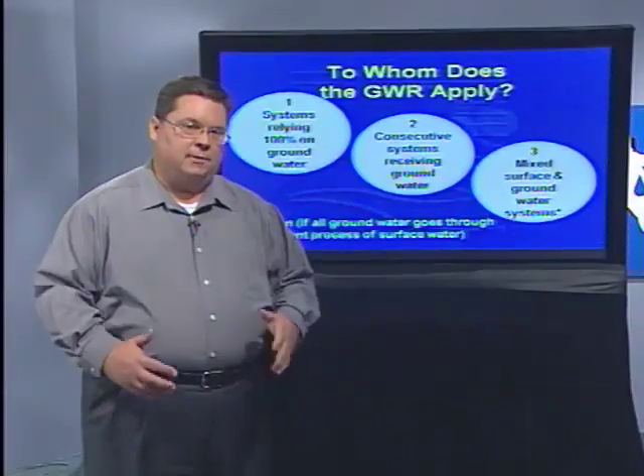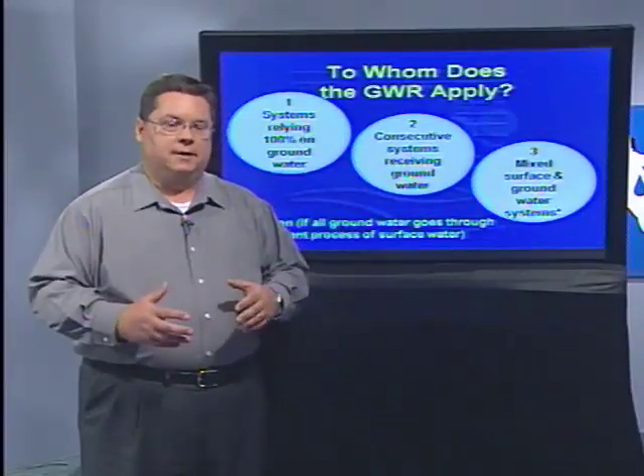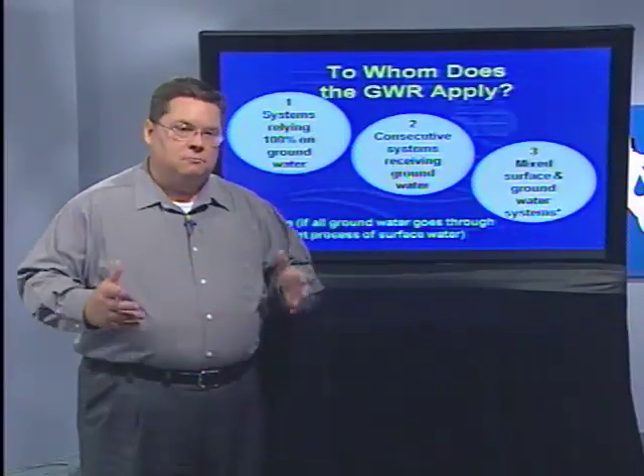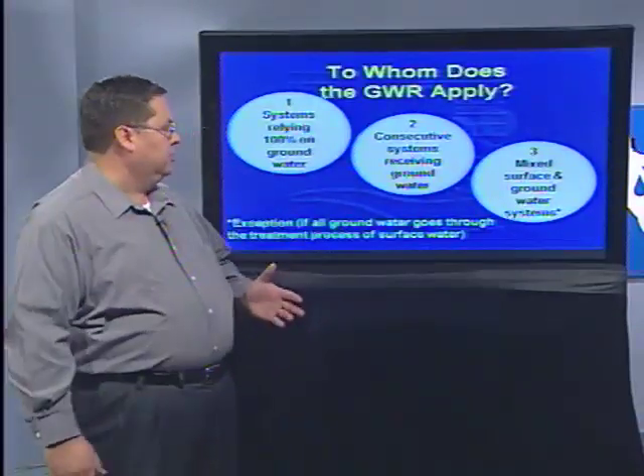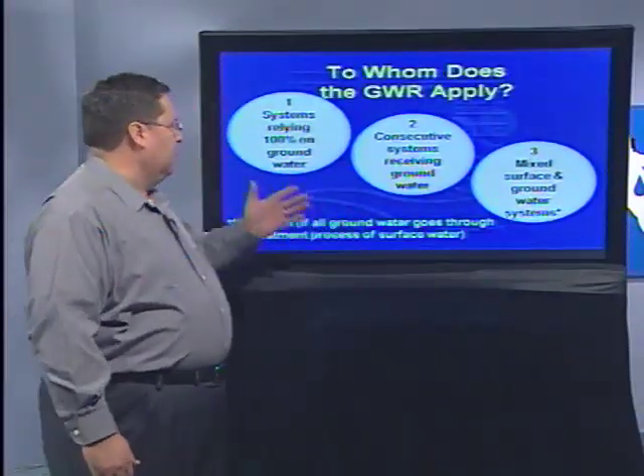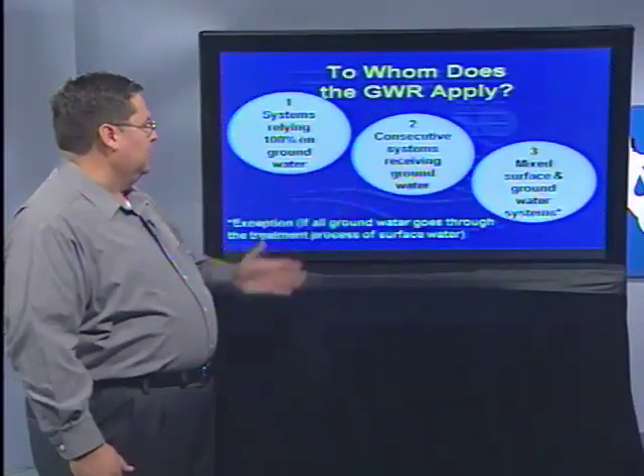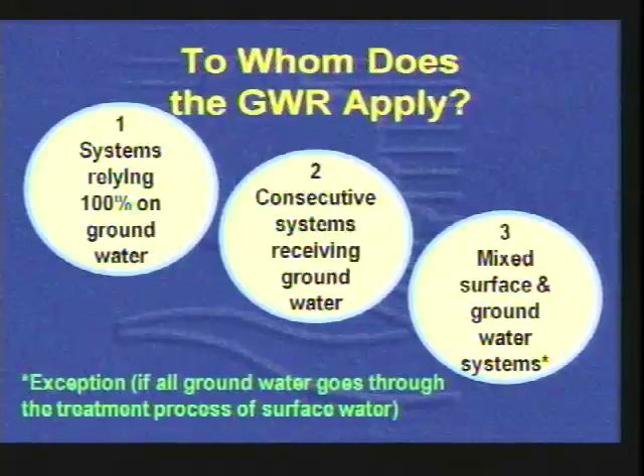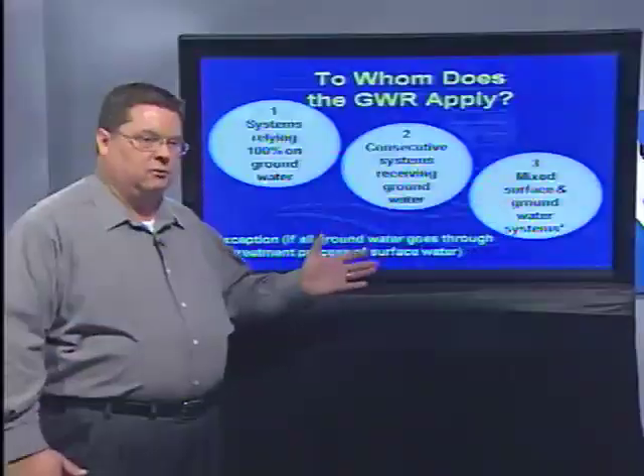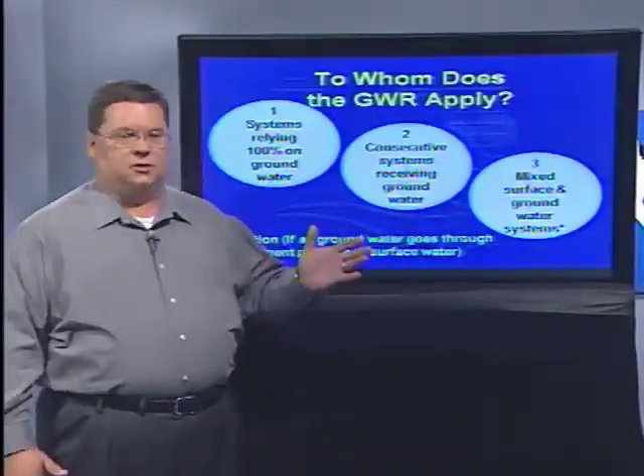Another big question we get almost on a daily basis is: does this Groundwater Rule apply to me? Here we have an illustration of the three basic things to consider. Number one is systems that rely on 100% groundwater. Also consecutive systems receiving groundwater. And also mixed surface and groundwater systems. The exception is if the groundwater goes through treatment to surface water standards.